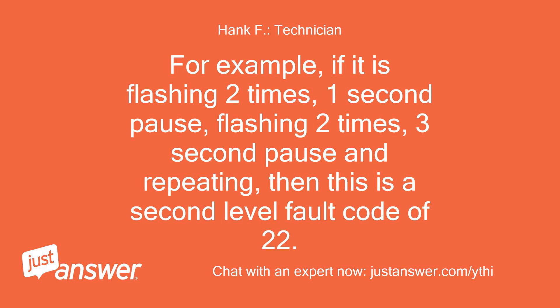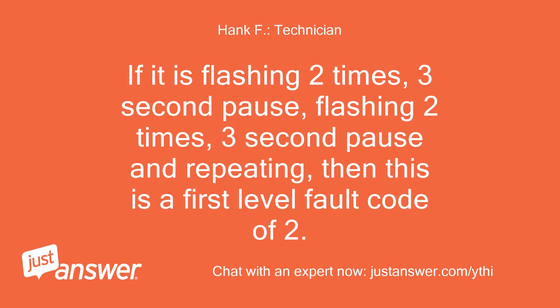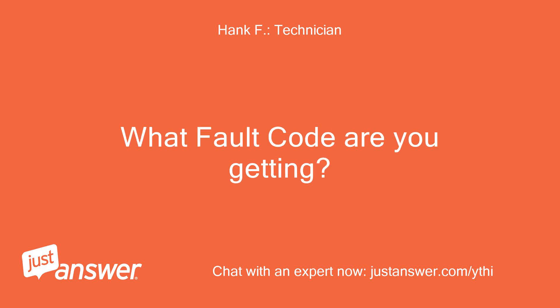For example, if it is flashing 2 times, 1 second pause, flashing 2 times, 3 second pause, and repeating — then this is a second-level fault code of 22. If it is flashing 2 times, 3 second pause, flashing 2 times, 3 second pause, and repeating — then this is a first-level fault code of 2. What fault code are you getting?